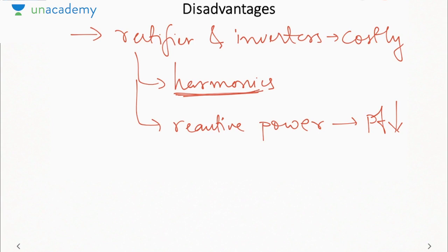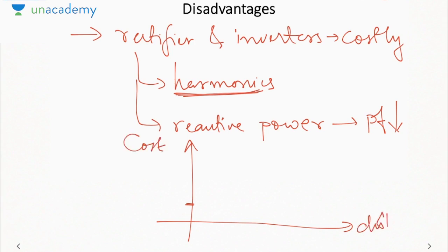That is why we only prefer it for higher distance transmission, otherwise the higher cost will not be compensated. So what happens is, suppose this is the cost versus distance curve. When distance is 0, the cost is actually the terminal equipment cost, that is, the equipment that you are using at the substation. That obviously will be higher in HVDC, because we need to use rectifiers and filters. So terminal equipment cost is higher in HVDC. So this will be DC, this will be AC.